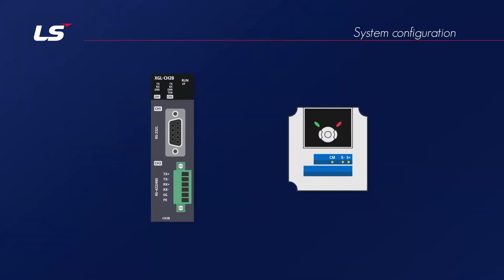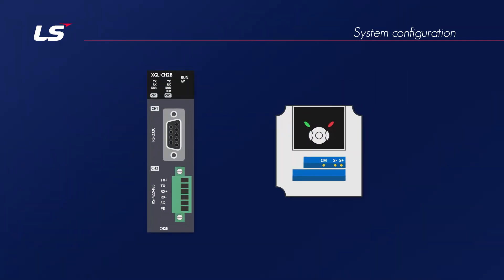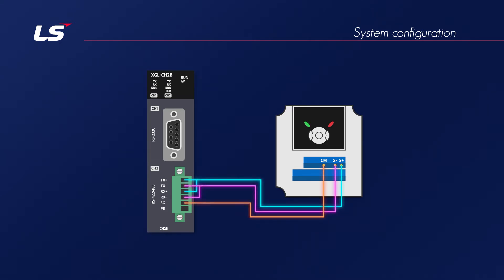RS-485 wiring between PLC and drive is as follows: connect TRX plus of PLC to S plus of drive, TRX minus of PLC to S minus of drive, and SG of PLC to CM of drive, respectively.